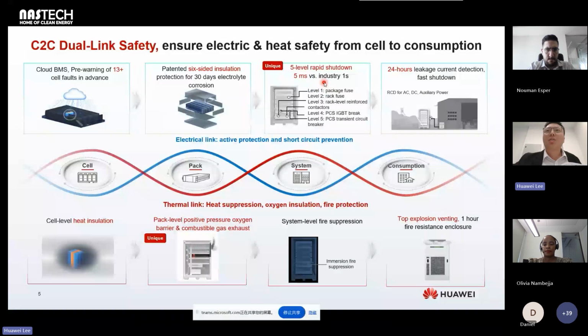One is package fuse, 2 is rack fuse, and 3 is rack-level reinforced contactors. Next is PCS IGBT break level, and level 5 is PCS transient circuit breakers. Other products may only have level 1, level 2, and level 4.